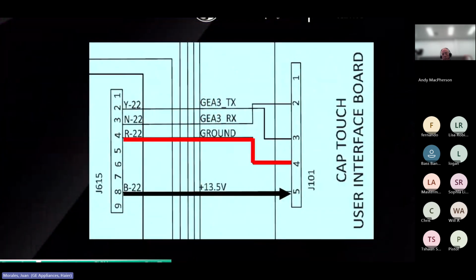But typically, if there's voltage coming out of the main, the problem is going to be the user interface. No voltage from the main means 100% you've got to replace the main board — that would be the fix. Again, if you use the schematic to guide you, you can't go wrong.